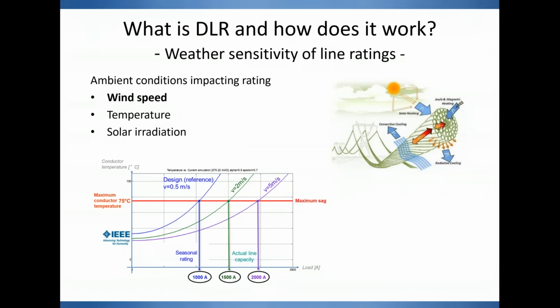Same effect with solar radiation, and the most important one, the one that has the largest impact by a very significant margin, is wind. When the wind blows on a conductor, even at low wind speed, it would take out the heat that is generated inside the conductor and cool it down, and therefore reduce its temperature and reduce its sag. And you can see on the graph that I've inserted at the bottom of the slide how that influence can be computed or simulated. And if you assume that a typical conductor would have a maximum operating temperature of 75 degrees, that's the example shown here.